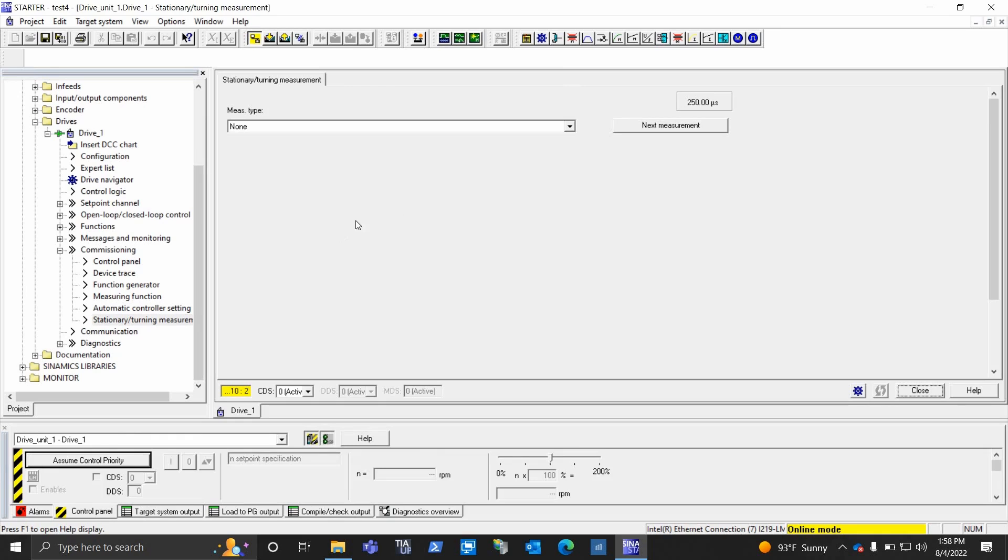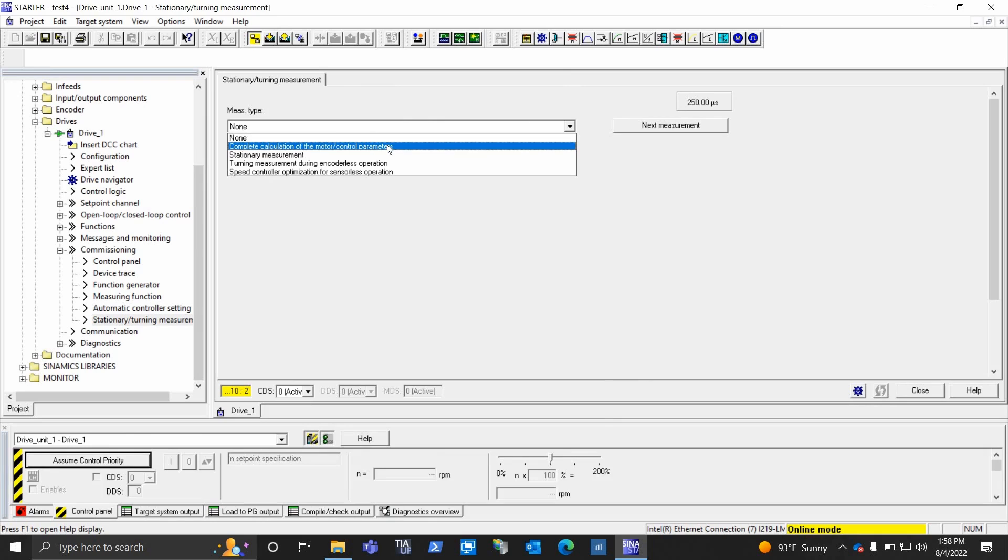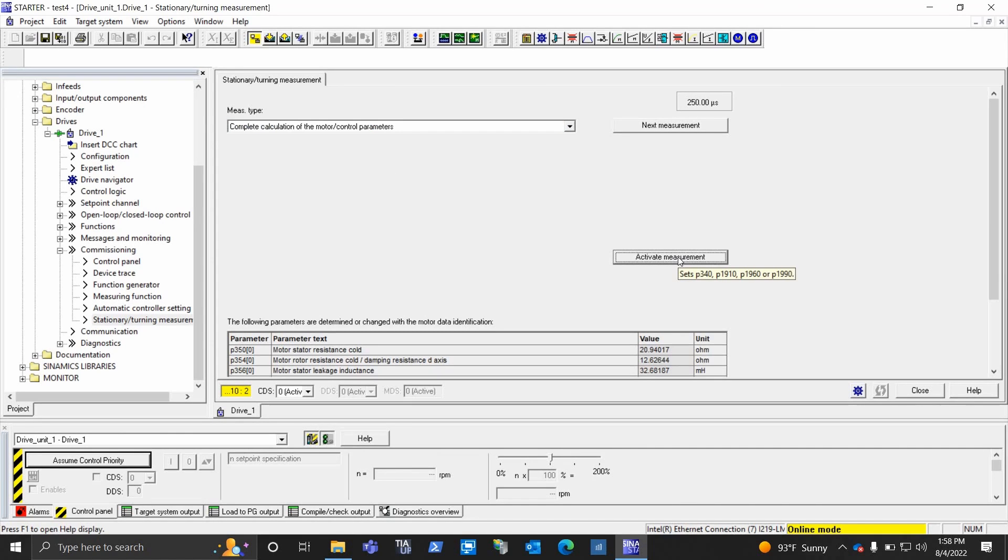Alrighty, so now topology matches. I've set it up for how I want the motor. Now what I want to do here is I want to go ahead and tune it, because it was tuned for another mode, you know, with an encoder. It just falls for some different mode. The tuning will not be optimized for the way the system is now. So I'm going to say first, go ahead and activate the calculations. It just calculates, it doesn't run anything, and it happens as soon as you hit the activate measurement, so it's done.